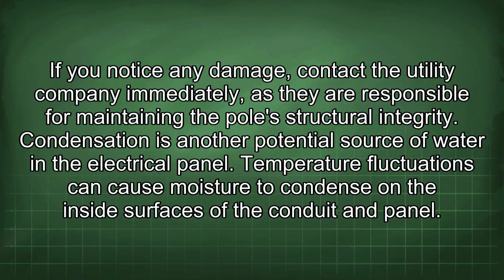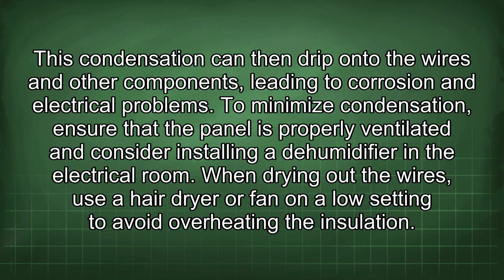Condensation is another potential source of water in the electrical panel. Temperature fluctuations can cause moisture to condense on the inside surfaces of the conduit and panel. This condensation can then drip onto the wires and other components, leading to corrosion and electrical problems. To minimize condensation, ensure that the panel is properly ventilated and consider installing a dehumidifier in the electrical room.